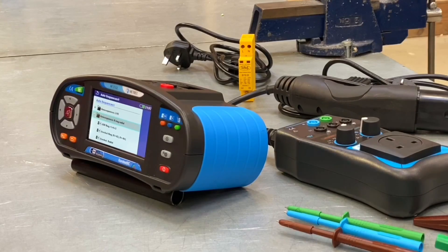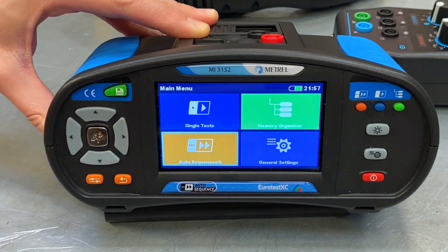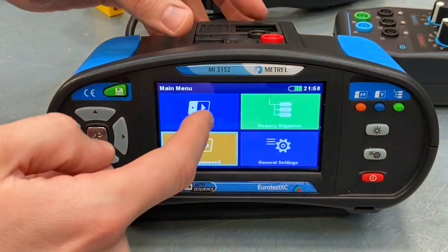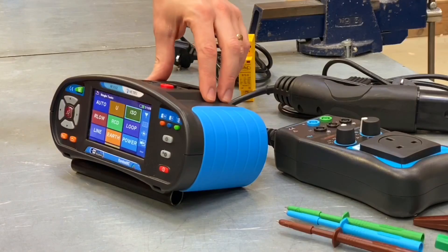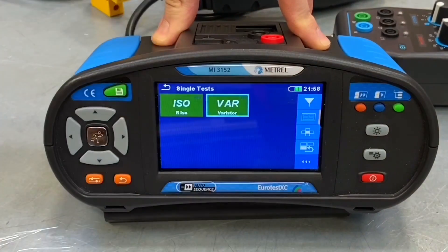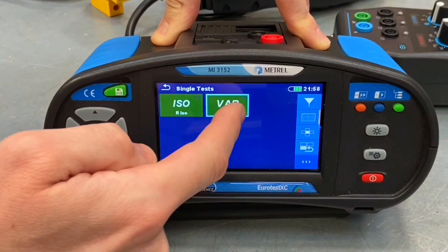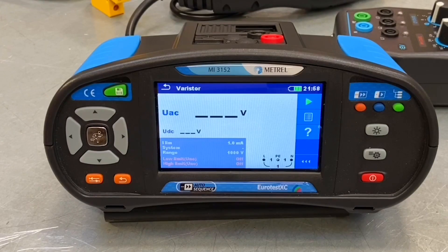Number two in our top 10: if we come out of this menu and go back to the main menu — press the back button or tap the screen — we're going to look in the single tests menu. With all the recent developments and changes to the regulations, we've started thinking about new types of protective device, in particular surge protection. If we go into the ISO menu, which is effectively the insulation resistance menu, we've got a VAR option which says VARISTOR underneath it. Clicking on that runs a test to check that your surge protection devices are doing their job properly.